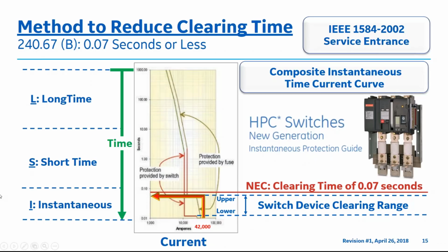Again, the electronic device utilized in this EasyPower presentation is GE's HPC2 device that meets the 2017 NEC 240.67 requirements for A, documentation, B, device having a clearing time of 0.058 seconds, and B2, a maintenance switch. The HPC2 meets the arcing current clearing time requirements of 0.07 seconds or less. HPC2 time current curves are available on the GE Industrial Solutions website with integral ground fault, as this device is intended for both normal or forward power distribution as well as reverse applications such as distributed energy resources.